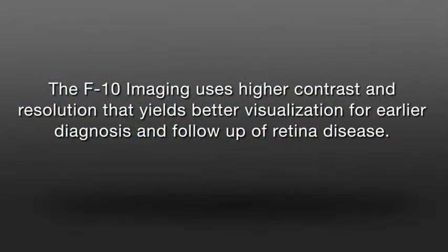Unlike other SLOs, NIDEK F10 has 4 colors for different penetration levels. The F10 imaging uses higher contrast and resolution that yields better visualization for earlier diagnosis and follow-up of retina disease.